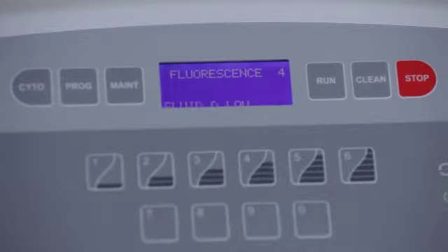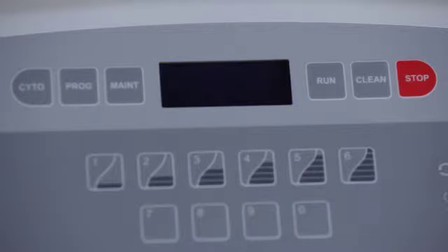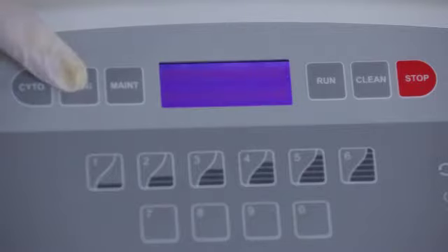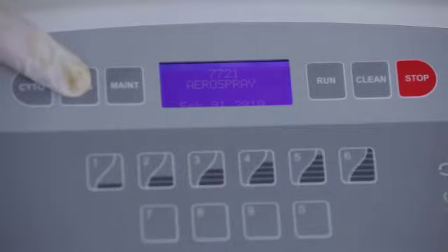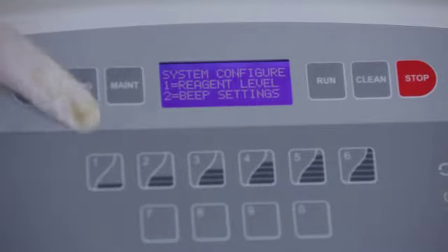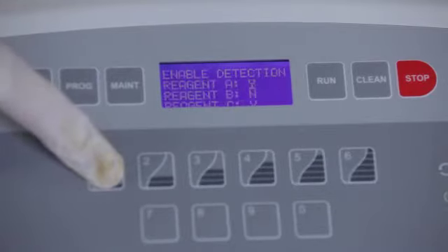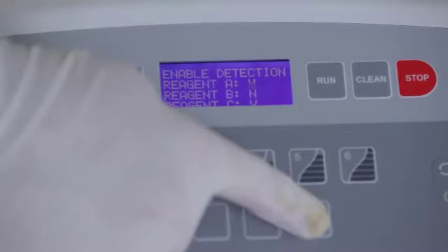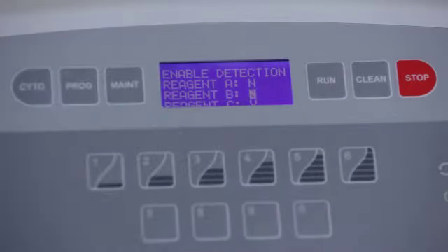After the 5-liter container is installed, the level detection for the D line should be disabled. It is disabled by turning the stainer off, then on again. Press Prog while the stainer is booting up. Press 1 for level sense, press 1 for enable disable, then press 1 for the A through C lines, and press 0 for line D. This will deactivate the level detection for the D line.